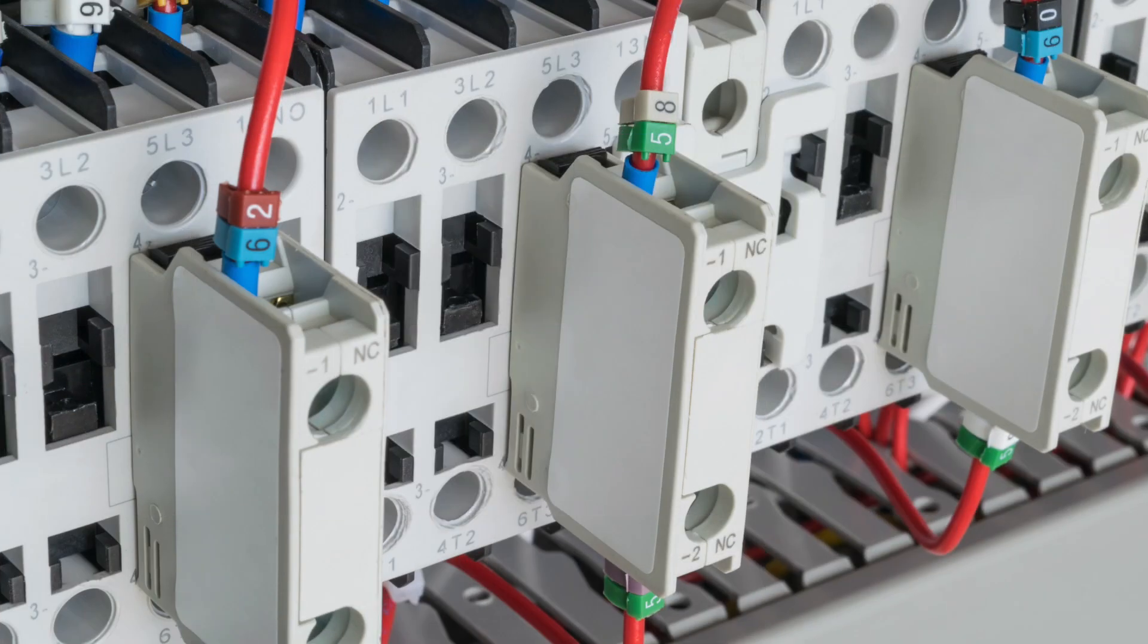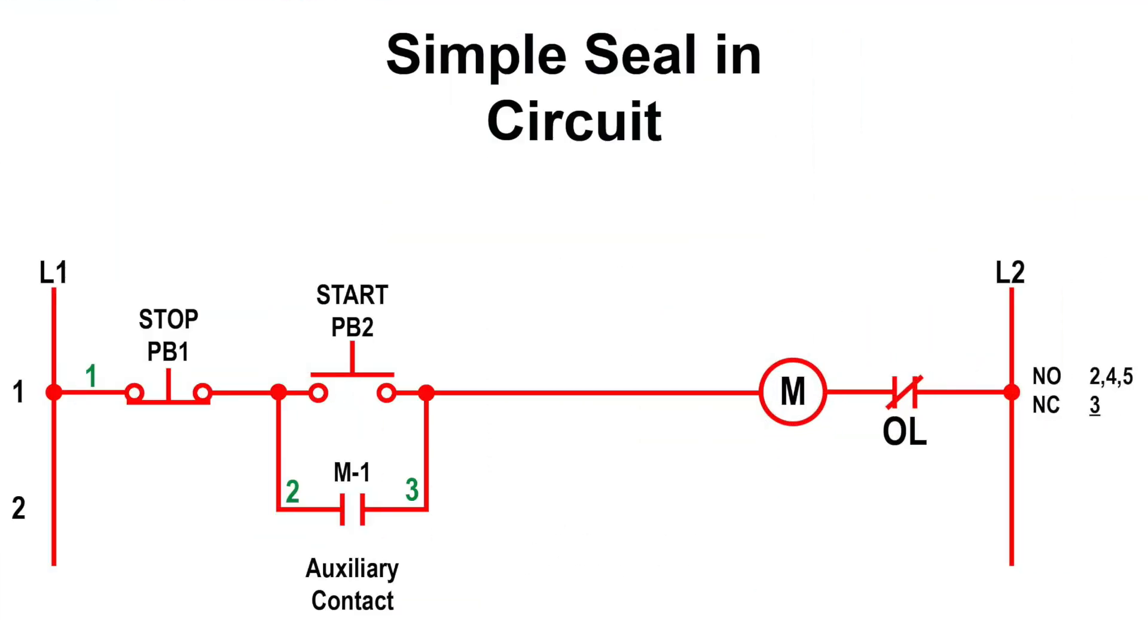Auxiliary contacts of a contactor have a much lower current rating than the main contacts and are used in control circuits for interlocking, holding, and status indication. The example provided shows auxiliary contacts being used to seal in or hold the motor, to keep it running after the start button has been depressed.